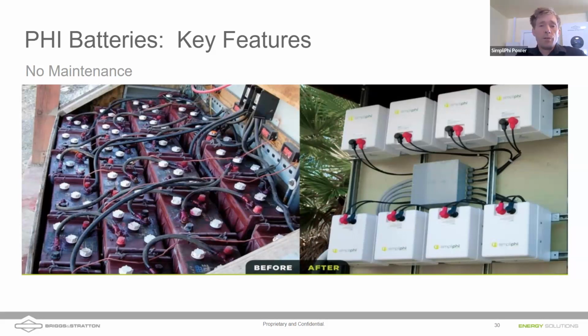Not if you use our recommended float charge. We recommend floating our batteries at 54 volts. We don't want to, and we definitely don't want to use equalize. If you have old charging equipment that used to equalize, the point of that was to provide a very high voltage on lead acid batteries to burn off the sulfate layer that could accumulate on the lead acid plates. So make sure not to use equalize, and set that float voltage at 54 volts for our 48-volt batteries, or 27 volts if you're floating a 24-volt system.